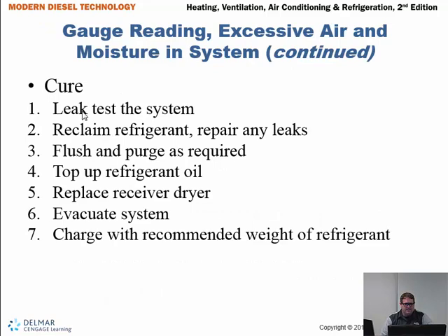So again, the cure: leak test the system, reclaim the refrigerant, repair any leaks, flush and purge as required, top up the refrigerant oil, replace the receiver dryer, evacuate the system, and charge with recommended weight of refrigerant.